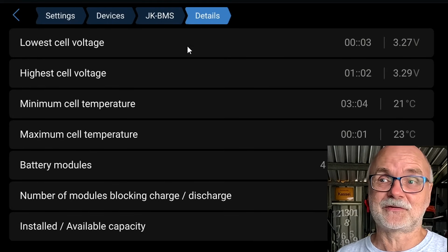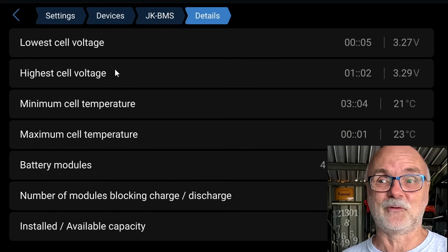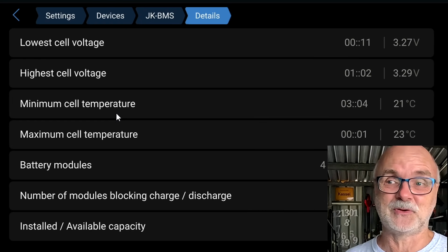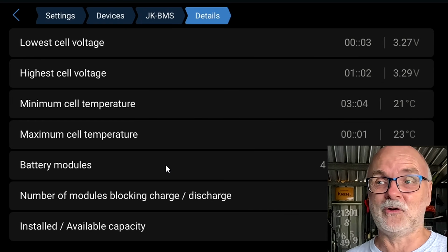These are pretty much the most important parameters the BMS requests or sends to your inverter. You may not be able to see all these details in your inverter itself, but it gets all these details, as shown here in the Victron system. For example, your inverter may not show the lowest and highest cell voltage, or the lowest and highest temperatures, or how many battery modules are online. But internally, it works with this information, as we will see right now.